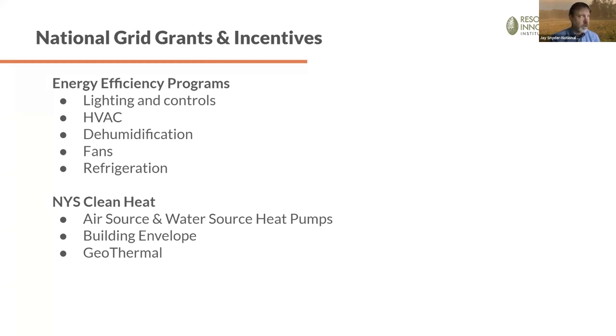There are building codes or energy codes involved with New York State. What National Grid tries to do is, in a case where there is a code minimum, we try to cover 100% of the incremental cost between that baseline item and the better item. So out of your pocket, you're paying for the inefficient item, but in reality getting the better item. So in the case of lighting, if you could buy a 1,000-watt metal halide for $100, but an LED light might be $250, we're going to try to cover that $150 incremental cost. That holds true for any type of equipment where there is a code standard available.